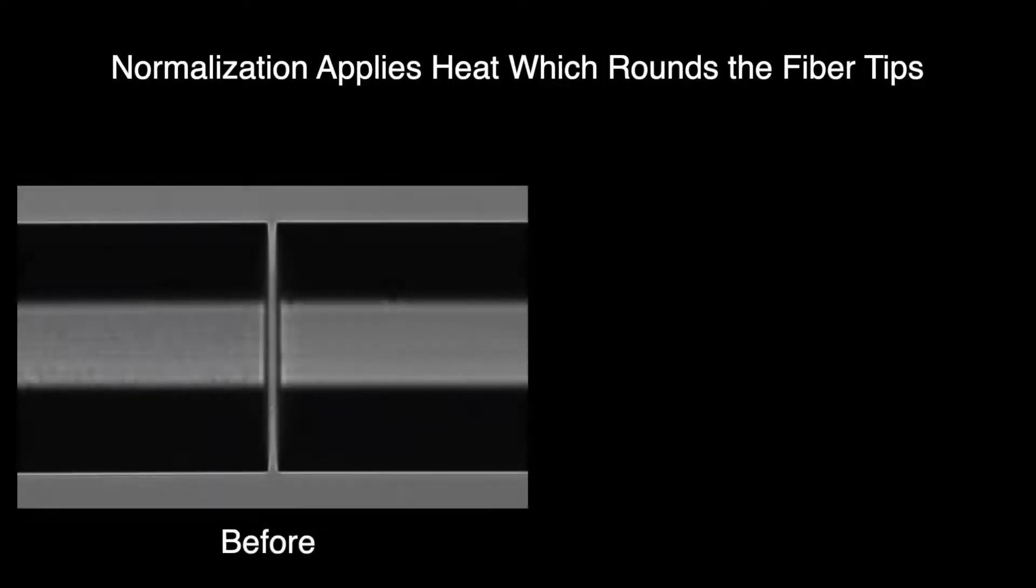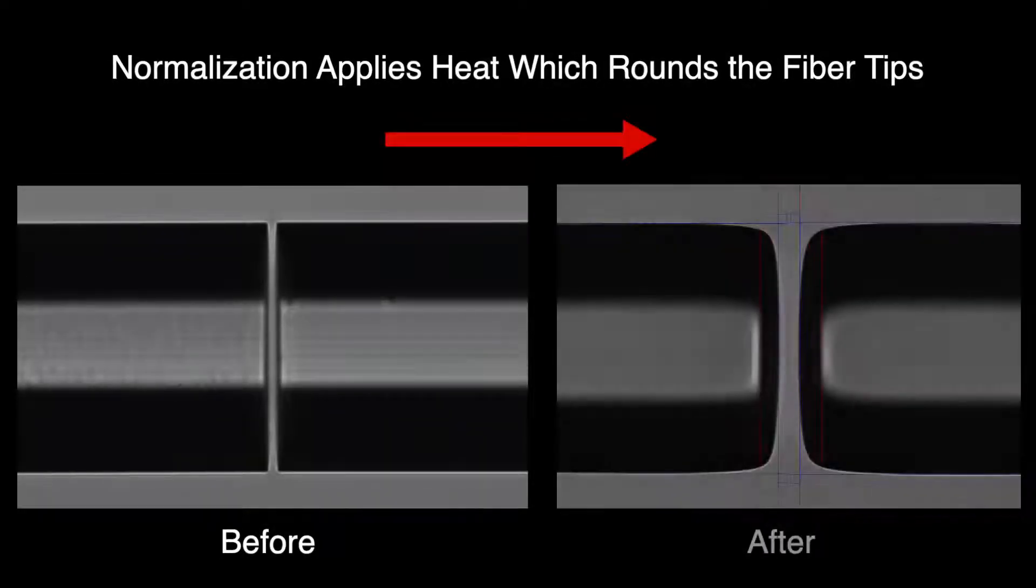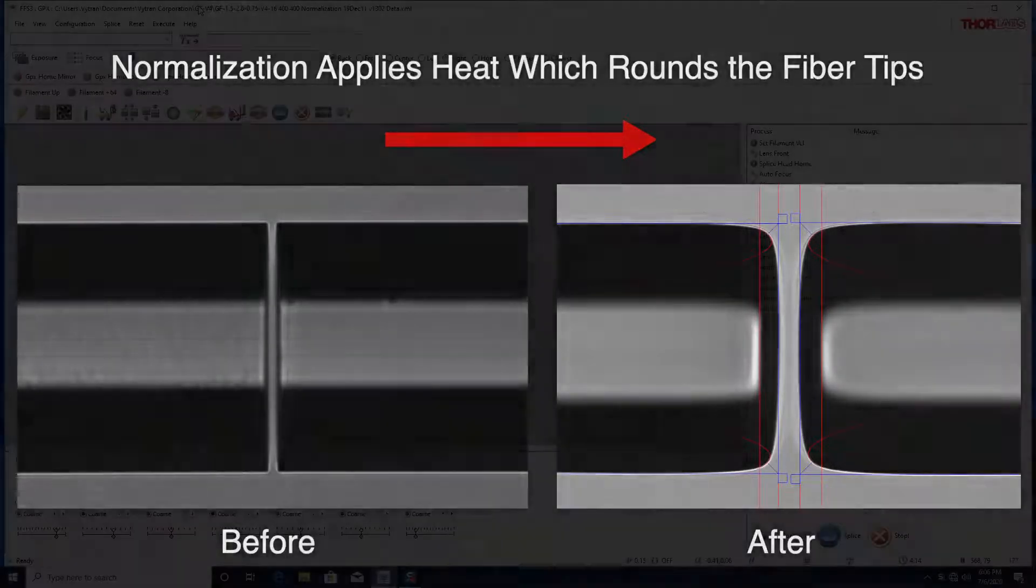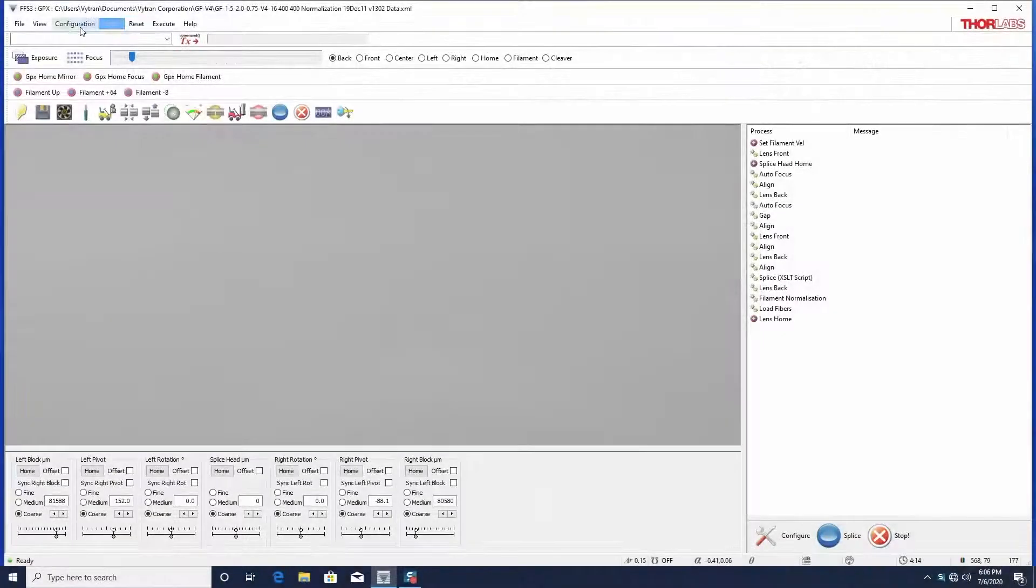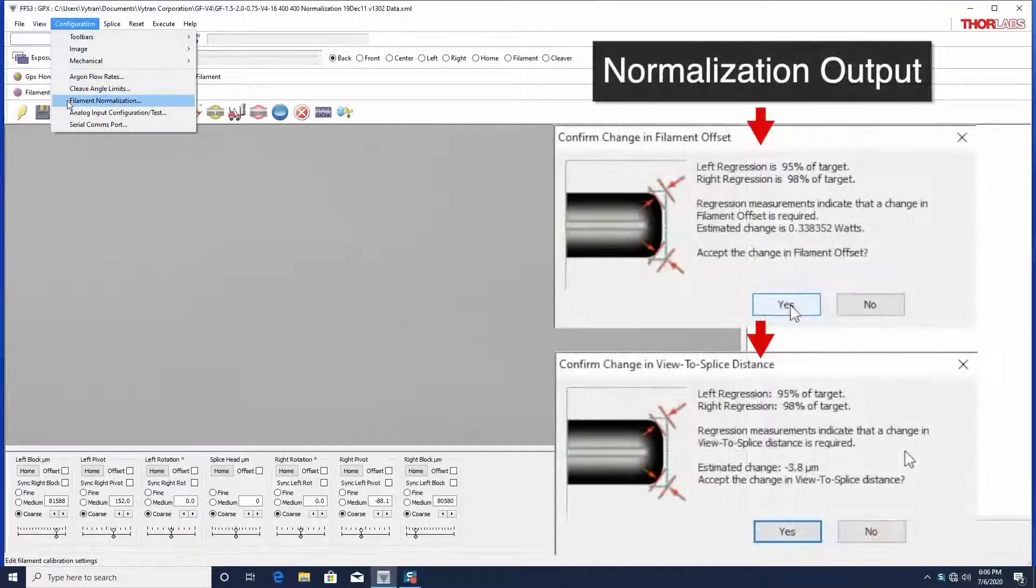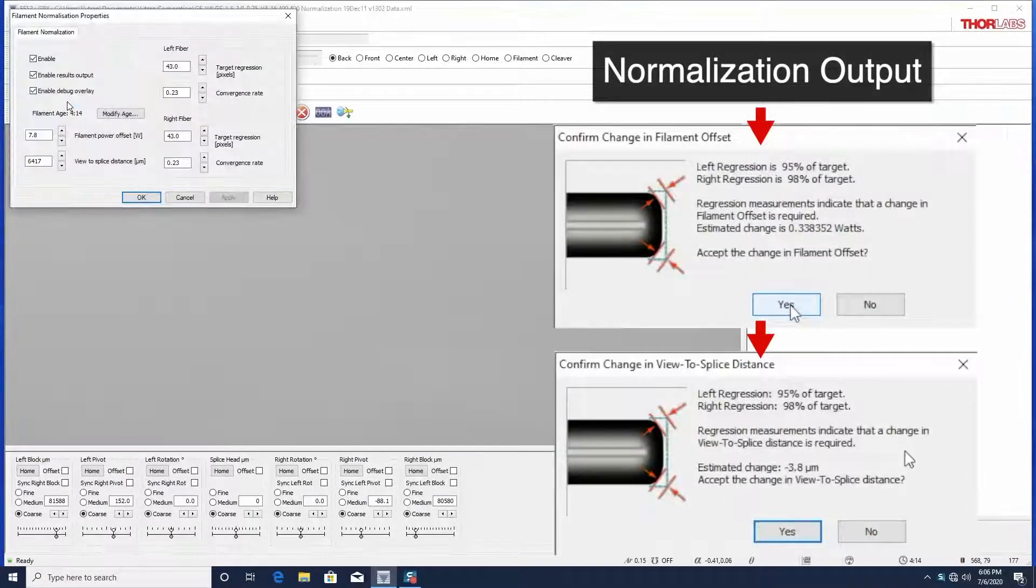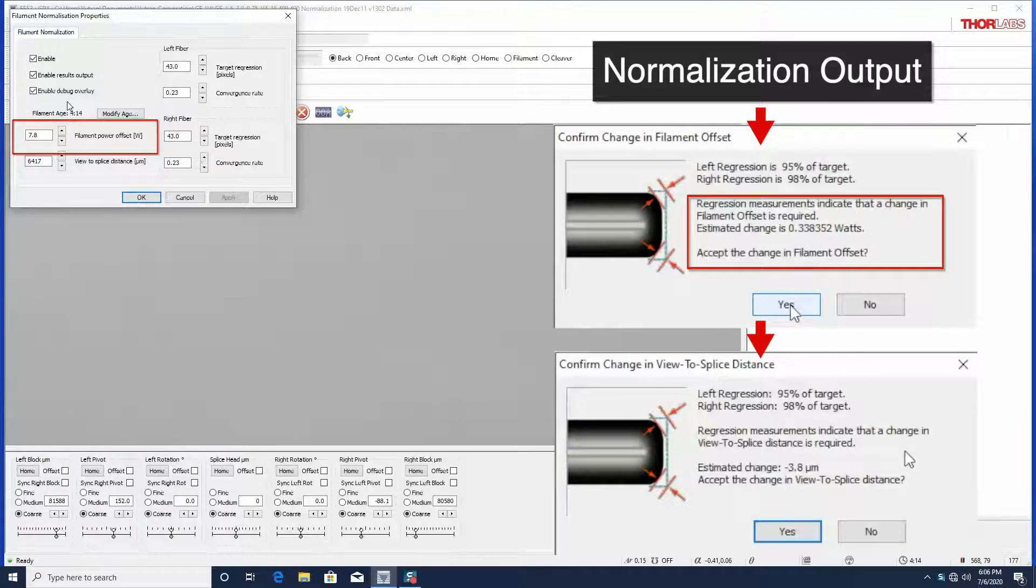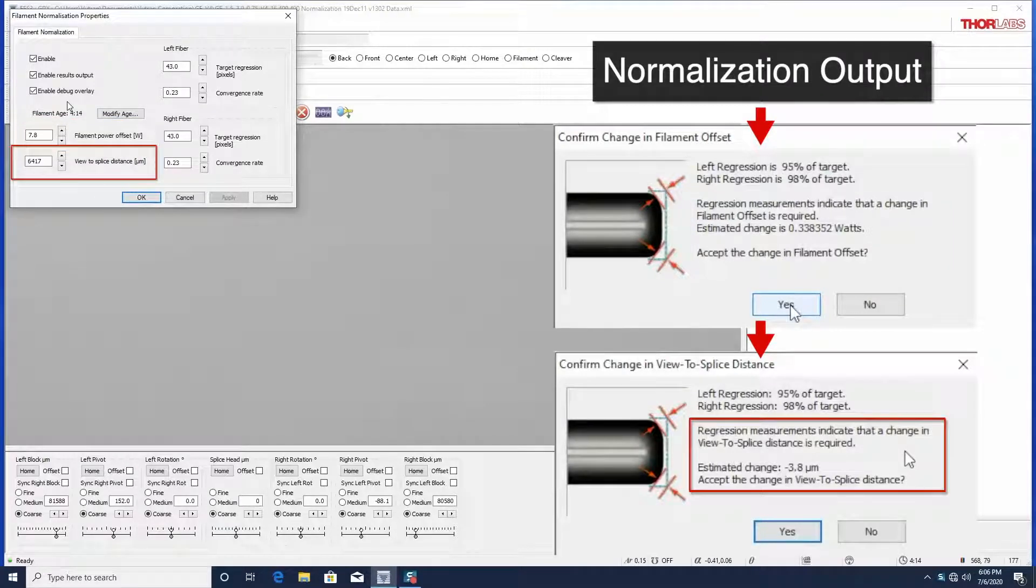Normalization applies heat to two flat cleaved fibers, which causes the surface tension of the molten glass to round the tips. Then, the software will recommend changes to not only the filament power offset, but also the view to splice distance.